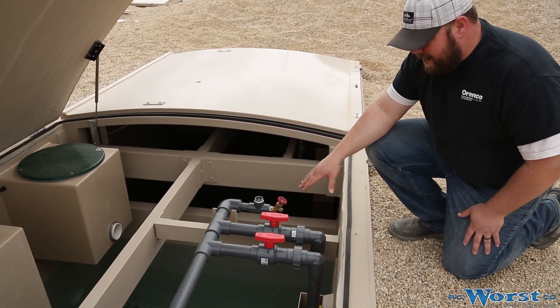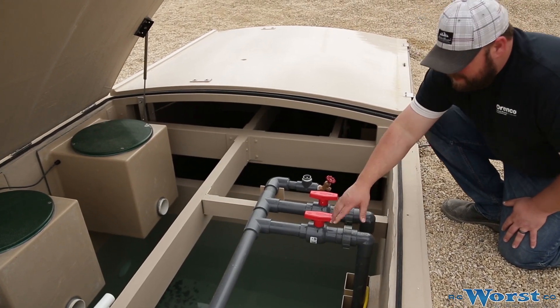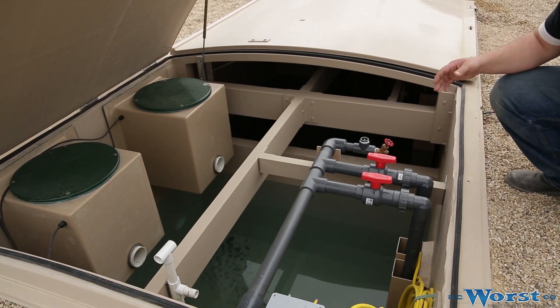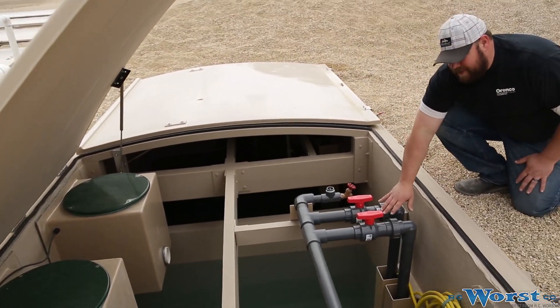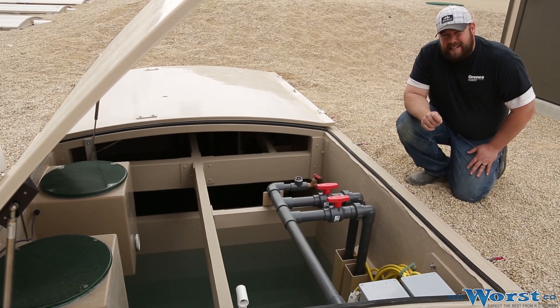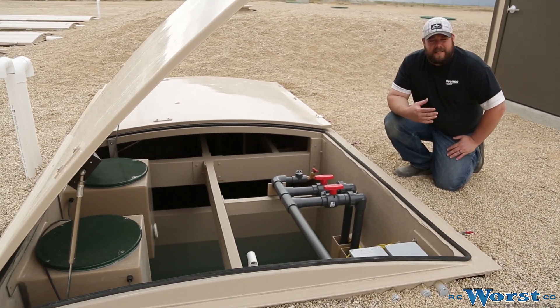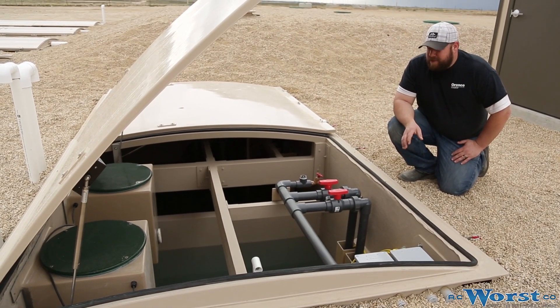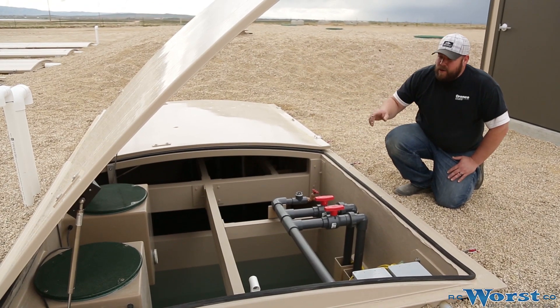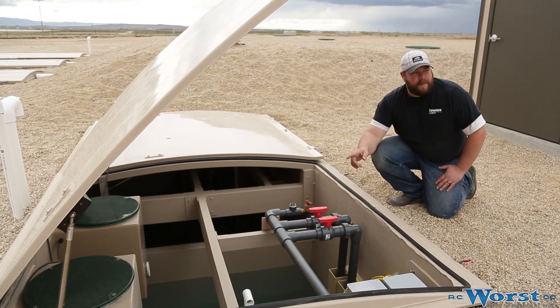The AXMAX Dose Tank is pretty straightforward. We have a pair of 75-gallon-a-minute horsepower-and-a-half pumps and floats here. As this chamber begins to fill up through the process, it triggers a dose which activates these two pumps. The critical piece here on the CSB project is we have a 19 total nitrogen limit. We're anticipating a high TKN coming in from the facility since it's mainly restroom waste. Even though we're going to get about 60% to 70% total denitrification through this process, we need a little extra help on the tail end, so these two pumps actually pump up through the building.